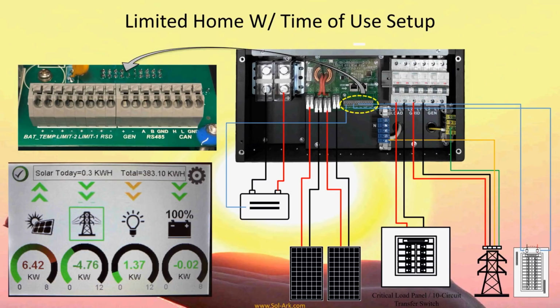So here we're doing more than just running these critical loads off of solar. We're going to actually do much more. We're going to actually sell back to the house. And this is called limited home mode or zero net export. What we do is we add these sensors on the mains of the whole house, L1 and L2, and we provide the sensors, and they get wired into limit 2, limit 1, and they need to be correct. So what we'll see is the solar will be producing and we'll be running our loads, but then it'll be selling back to the rest of the house to cancel out a big air conditioner in the house or some other loads. And so it's pretty similar.